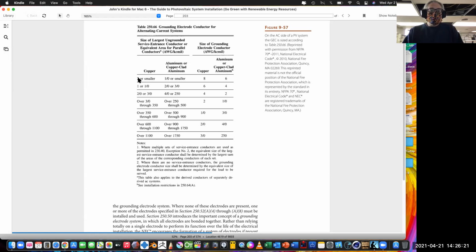If we're using copper wire, which we were, that number 6, which is 2 or smaller, tells us that we need a copper electrode that is number 8. So we drive that in the ground, and now we know what the size of our green wire is supposed to be. It's really that easy in most cases.